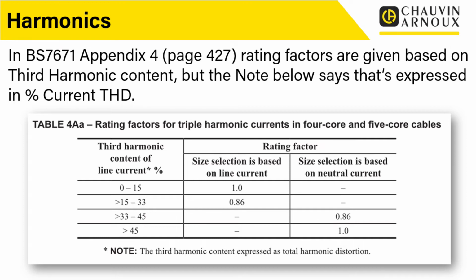So what's going on here is actually we're applying rating factors based on the percentage THD. So you can see that 0 to 15%, there's no real factor in there. It's just a factor of 1. So it doesn't really make any difference to that. If it's greater than 15 up to 33%, we're applying a factor to the line current of 0.86. And then once we go over that, we start applying these factors to the neutral currents. So again, this is where it starts to get more involved really from that side of things.